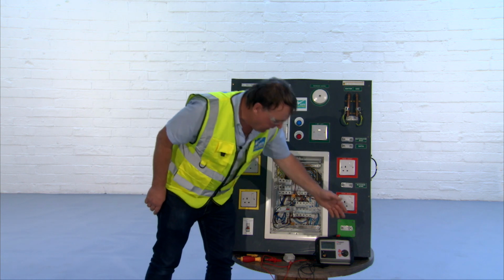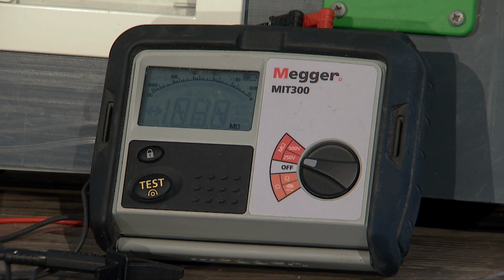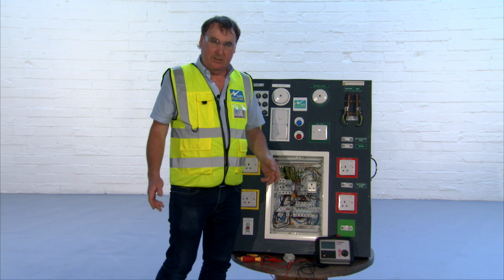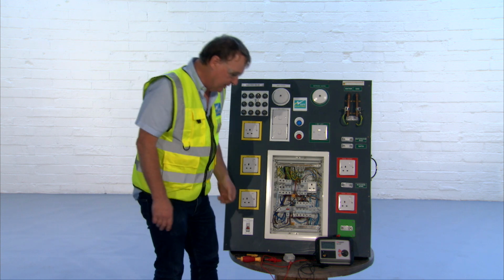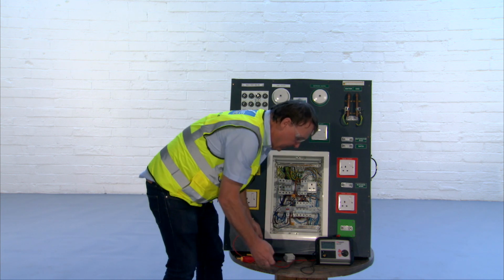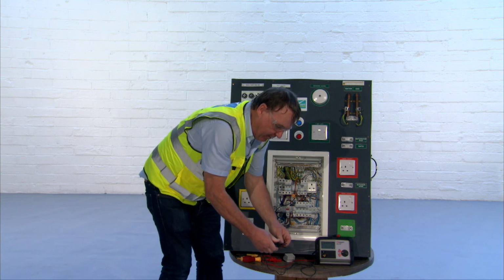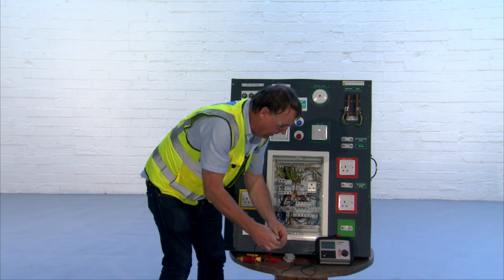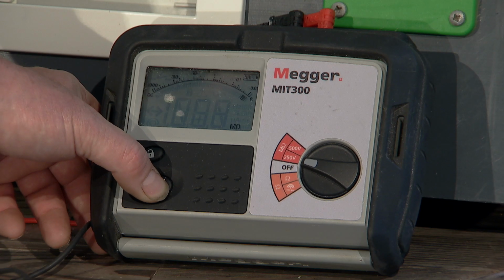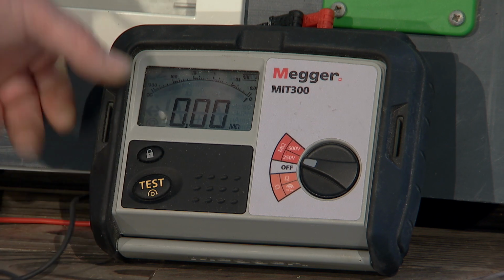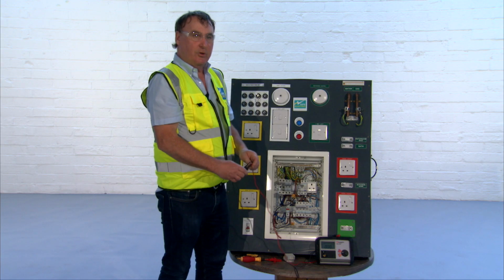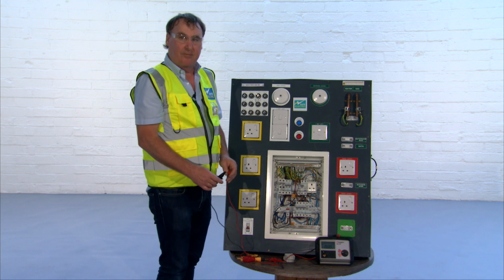And I have my meter set at insulation resistance, 250 volts. We would always recommend we start the test at 250 volts in an existing installation. Check that your meter is operating correctly. Join the two leads together. Press the button, and the meter should read zero, which it does. We have a functional meter and a functional set of leads.